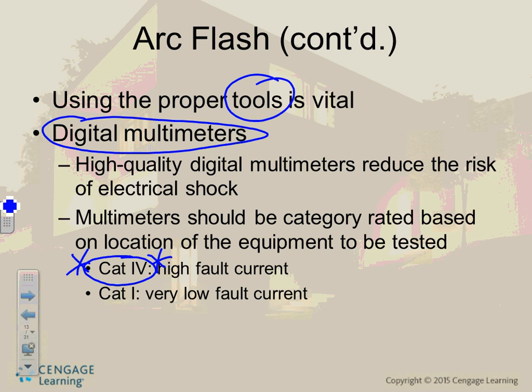You open a panel like this, you need category 4. What's category 4? It can handle higher fault current, and also transient. There are stories, guys, of people opening a panel, just measuring the voltage, and lightning hit the transmission line. A transient jumped into the line and caused a big explosion through their meter. They panicked when the meter started smoking, let go, and it escalated into an arc inside the panel. Now you have an arc flash, a big ball of fire that killed a fireman and the electrician working on it at that time. There are stories about meters that aren't rated for the work being done.